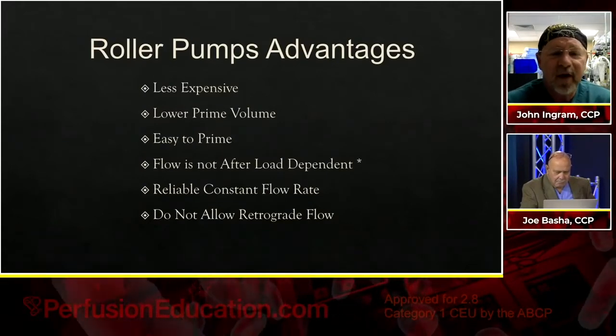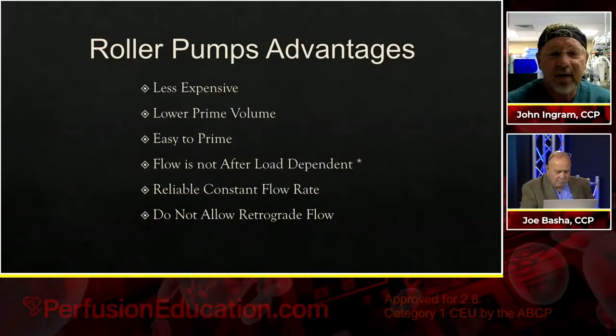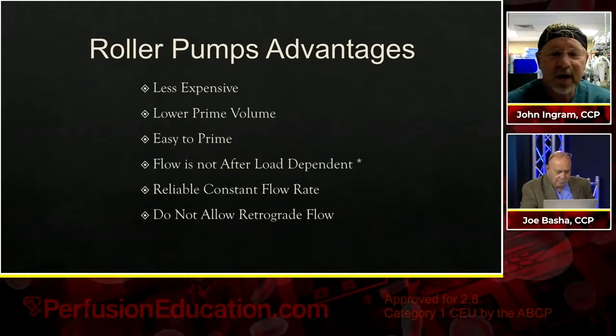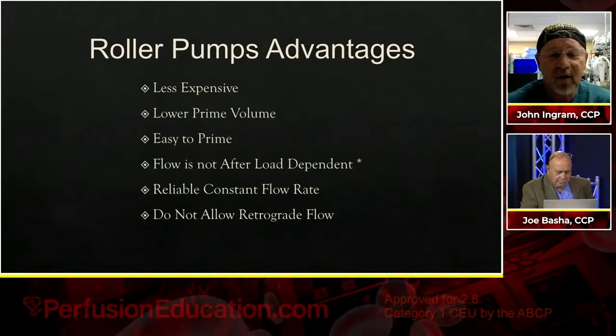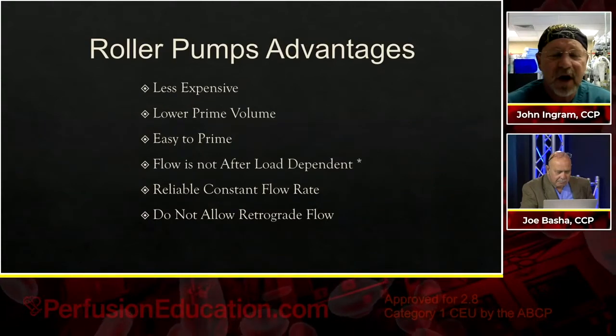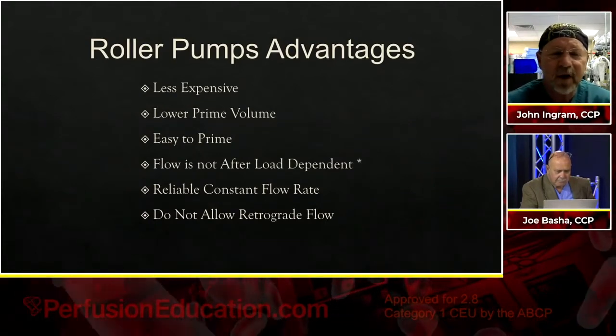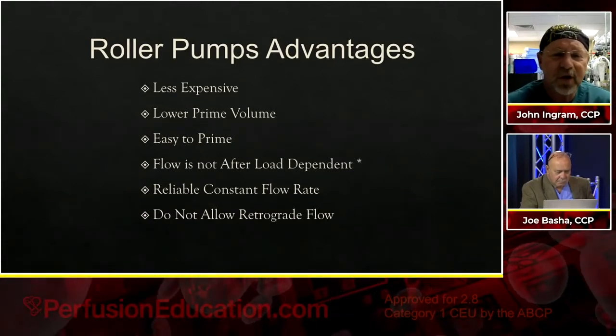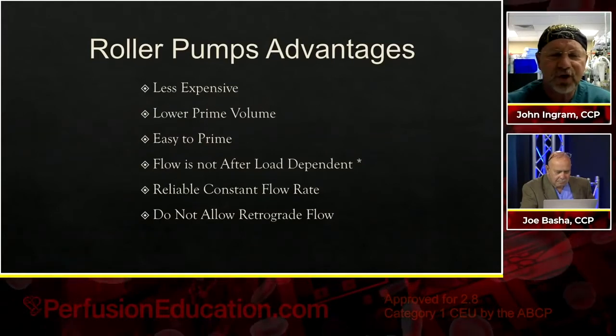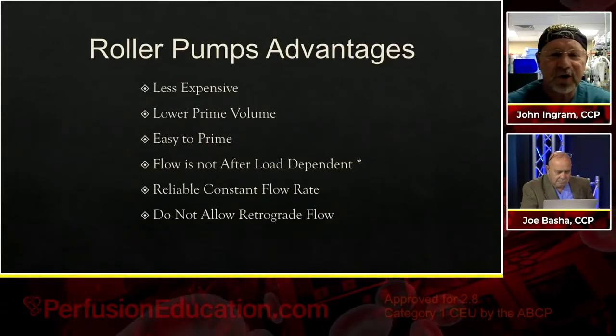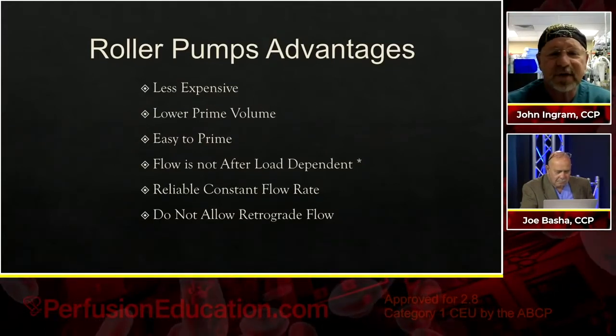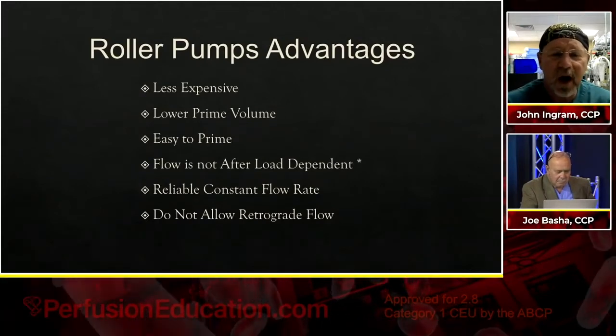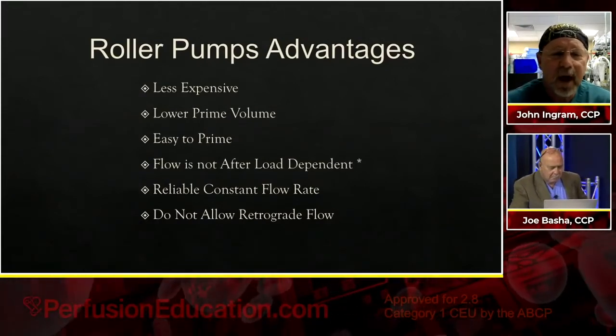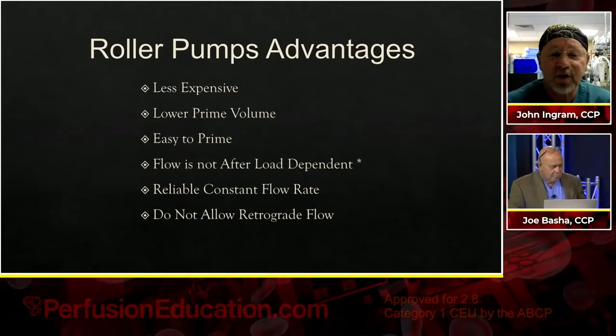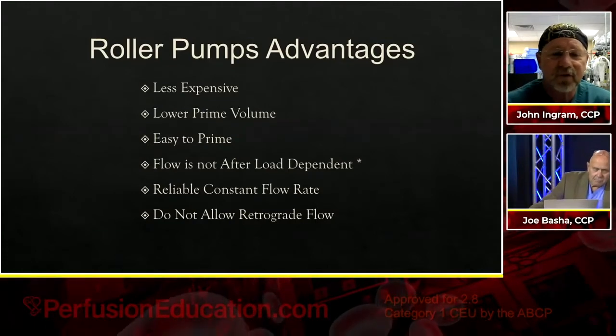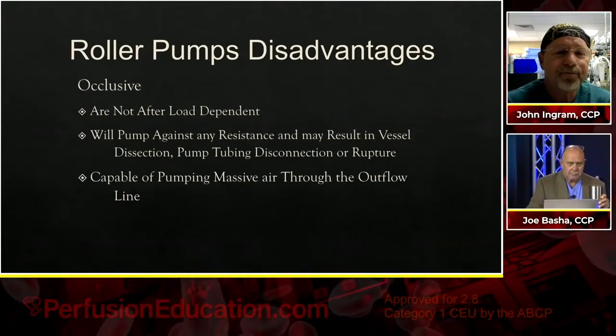Another advantage is that the flow is not afterload dependent. Now, I put an asterisk to that because that can also be a disadvantage, but the fact is that if you're flowing normally and things are normal, as the pressure and resistance in your patient changes, this flow is going to stay the same. It's a reliable, constant flow rate, and it does not allow for retrograde flow, something that centrifugal pumps can allow.